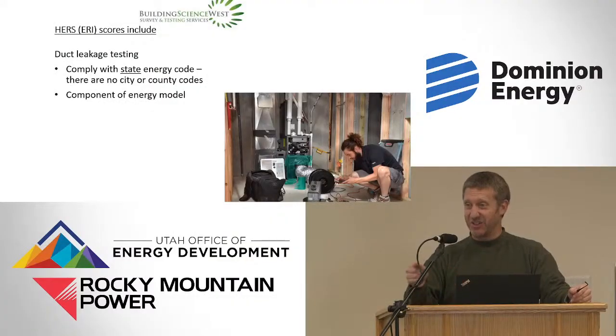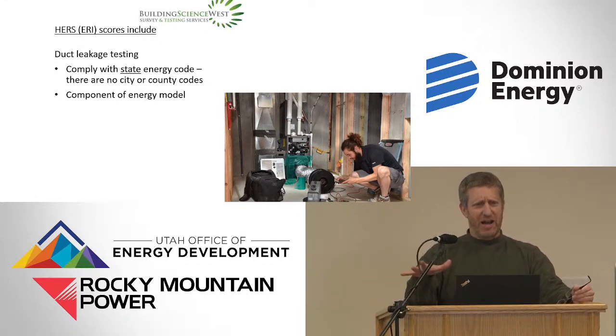Okay, so the duct leakage is part of the energy model. It really is quite important, especially if your ducts are in unconditioned space, that they be tight, because you're leaking conditioned air into unconditioned space. Most of our attics in Utah are vented, and so typically, at least in the winter time, they're pretty close to the outside temperature.